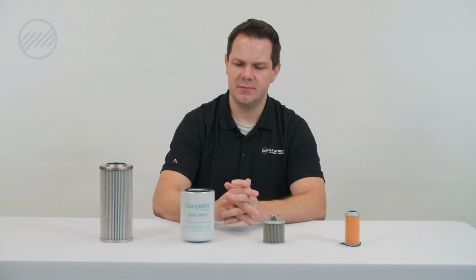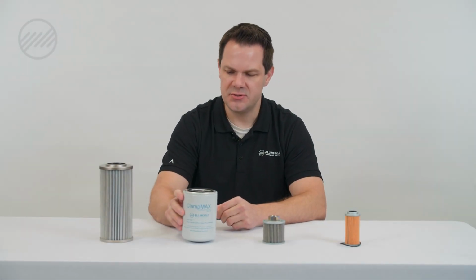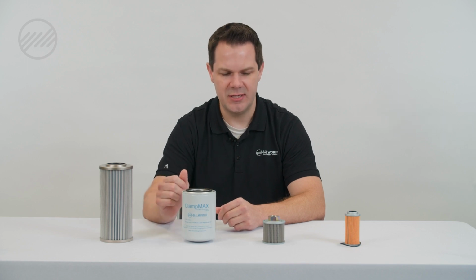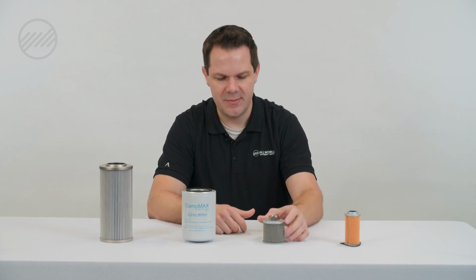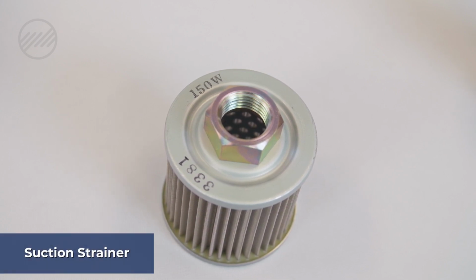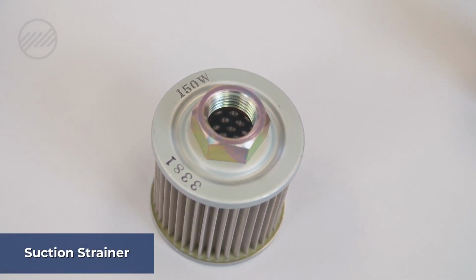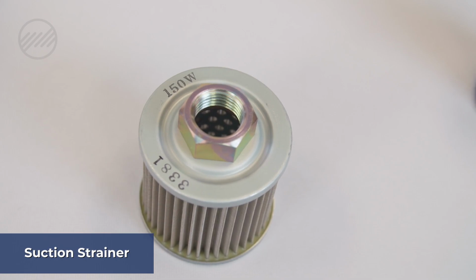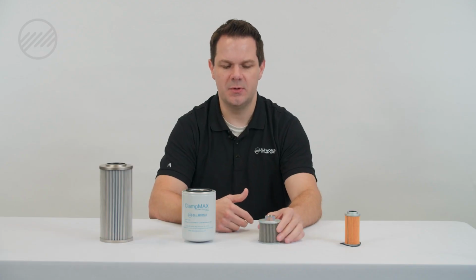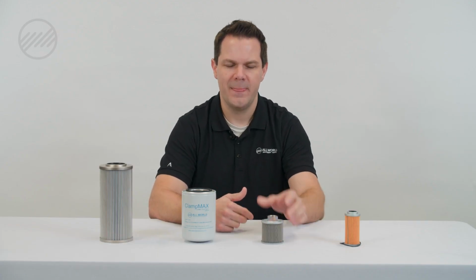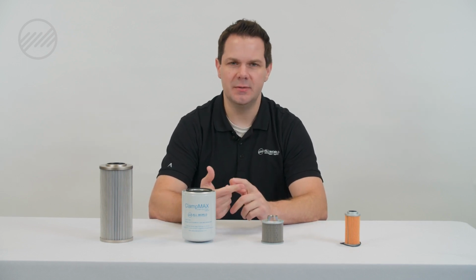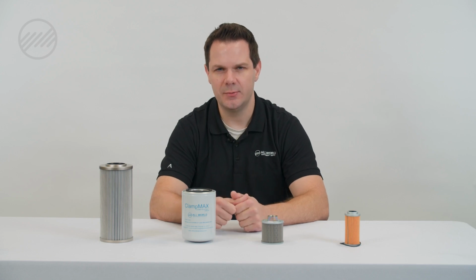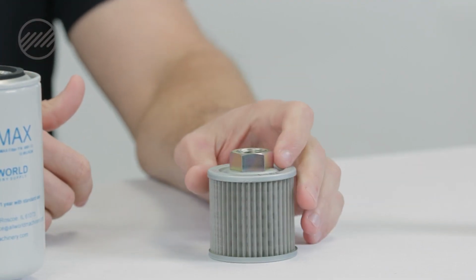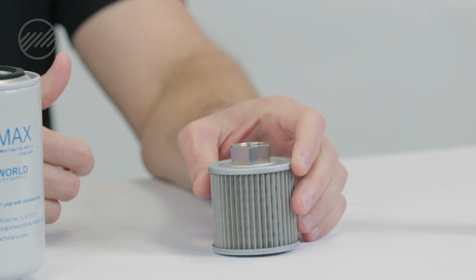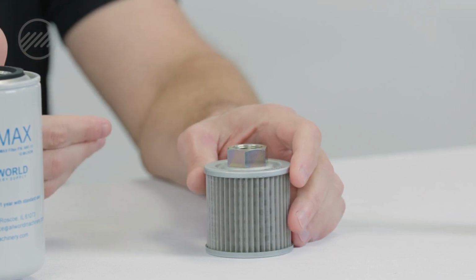Some of these items are used specifically in certain applications or in certain places. For example, this one here, commonly referred to as a suction strainer. A lot of your hydraulic systems or hydraulic power units will have this type of filter. If you're having issues with your pump building pressure, or it has just stopped working, it's always a good idea to check to see if there is a suction strainer that exists and its condition.